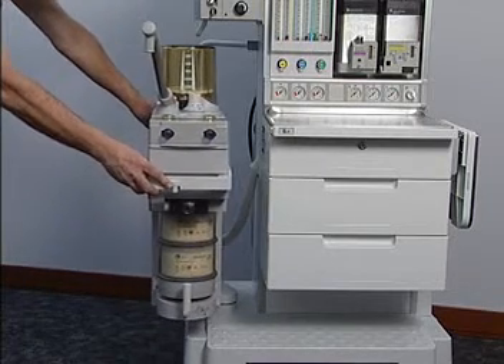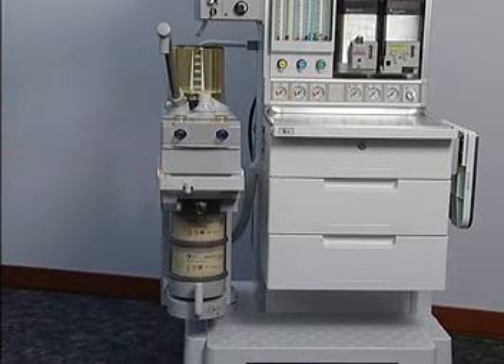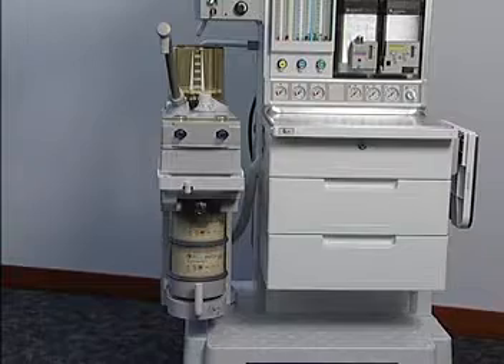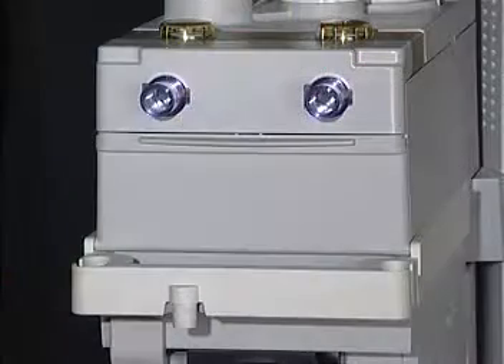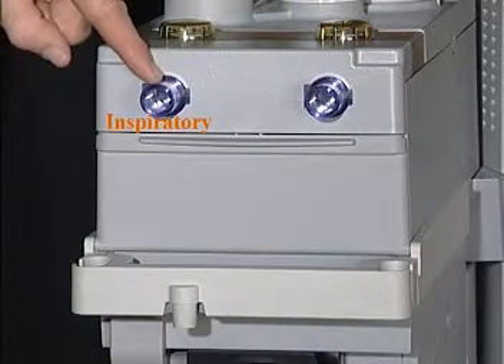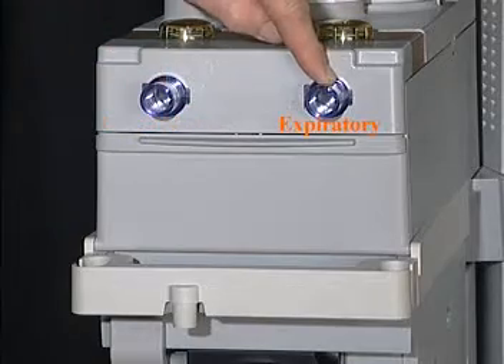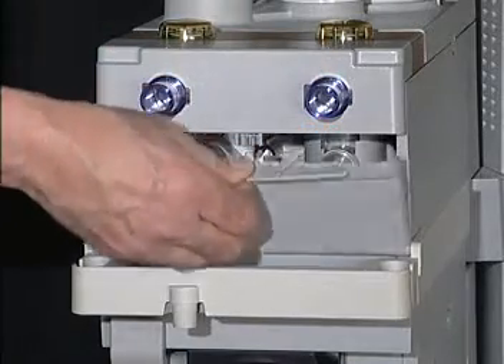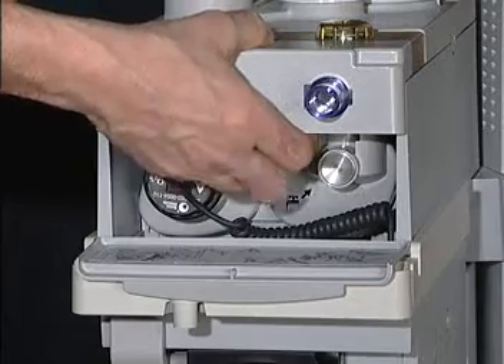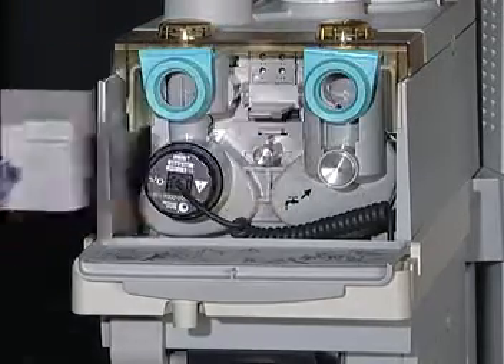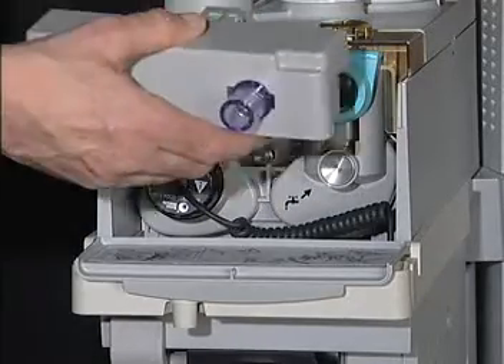Smart sensors and switches provide communication between the breathing system and the ventilator. The inspiratory and expiratory ports of the breathing system are actually the flow sensors, which provide feedback to the ventilator. They are protected in a manifold and can be easily removed and replaced by the user without the use of any tools.